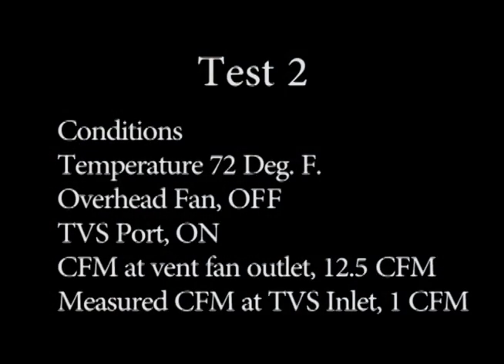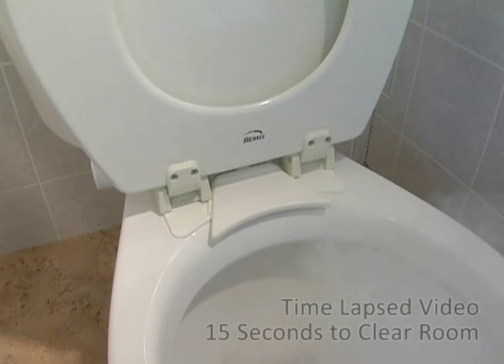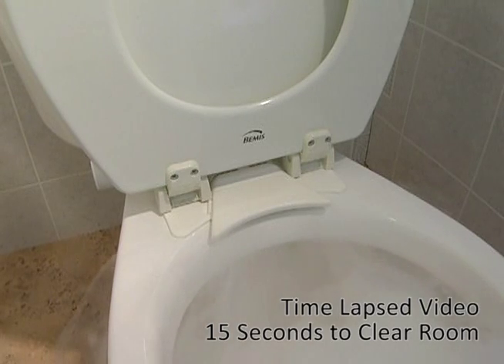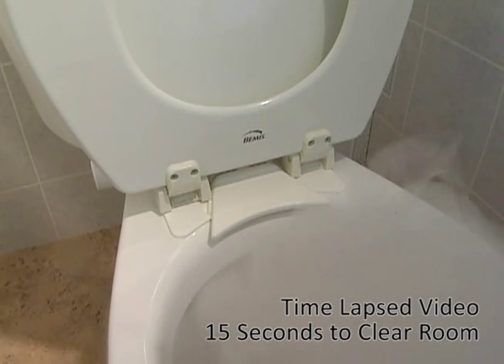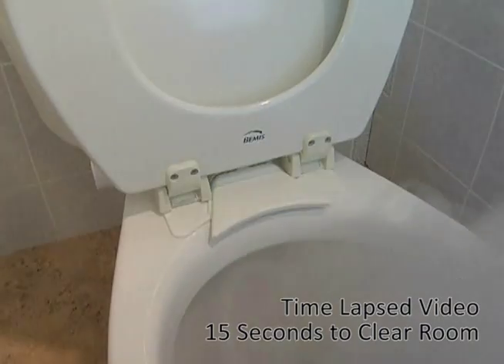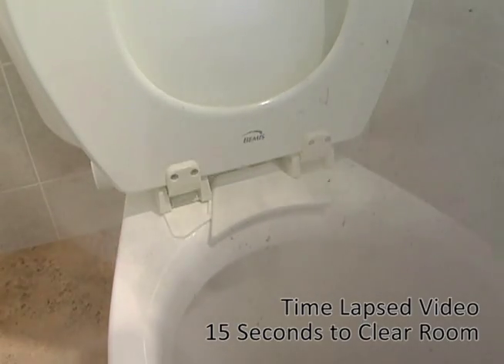Test 2. Test 2 simulated the condition where only the TVS system was connected and operational. The test smoke entered the test chamber through the toilet bowl. It first filled the bottom of the toilet bowl. No visible constituents of the test smoke overflowed the toilet bowl.